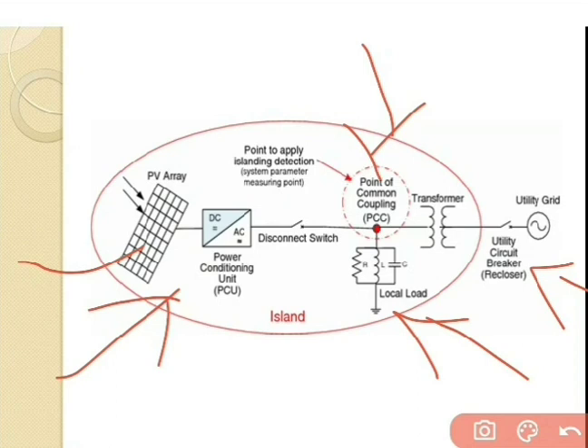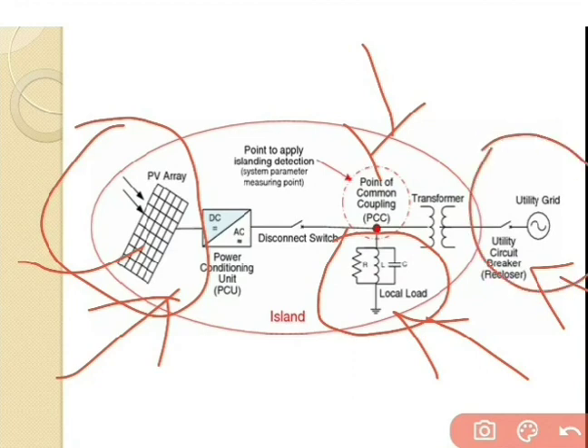What is the role of islanding? If there is any loading condition, unbalancing condition, or over-voltage condition at the load side, it can damage the distributed generator as well as the grid side. To protect the system, there is a component at the PCC inside which a relay and different kinds of circuit breakers are connected. If any unbalancing condition occurs in the voltage at the load side, that signal is sensed by the relay, which then sends the signal to the circuit breaker. The circuit breaker, based on the condition, protects the distributed generator as well as the grid side. This is the main function of islanding protection.